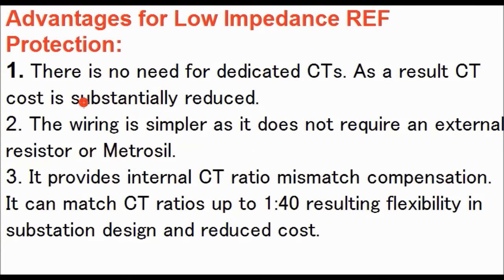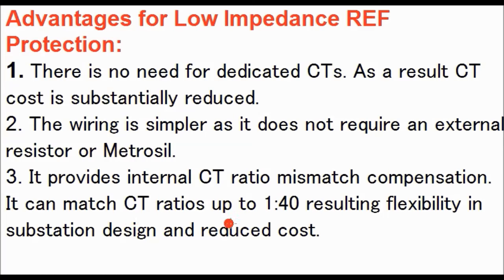The advantages of the low impedance type restricted earth fault relay are: first, no dedicated CTs are required as were needed for the high impedance type, substantially reducing CT cost. Second, the wiring diagram is very simple as it does not require any external resistance or varistor, and no resistance value calculations are needed. Third, it provides internal CT ratio mismatch compensation by the K factor, and can match CT ratios up to 1:40, resulting in flexibility in substation design and reduced cost.